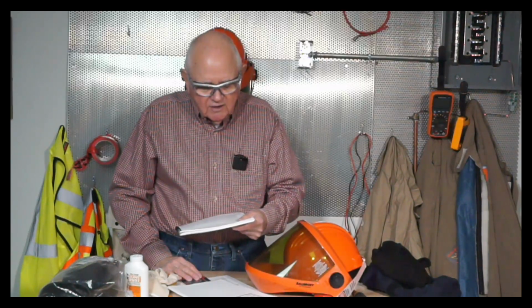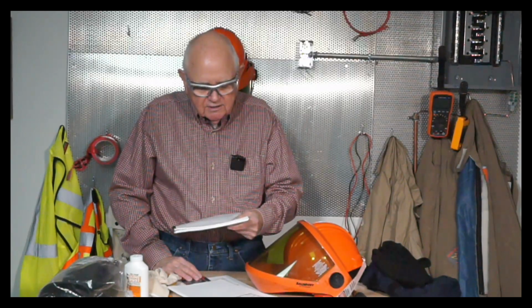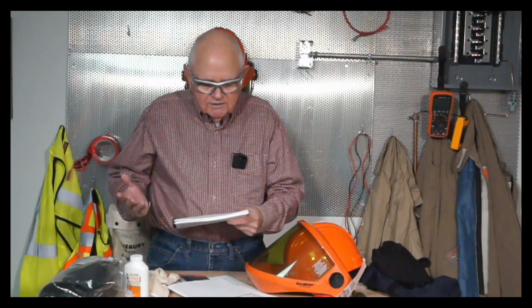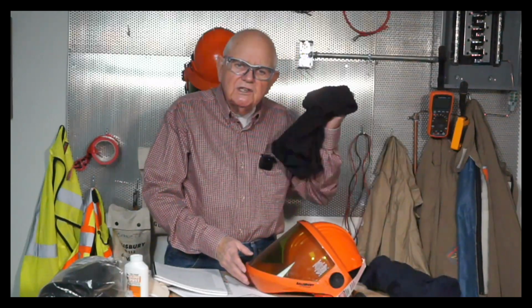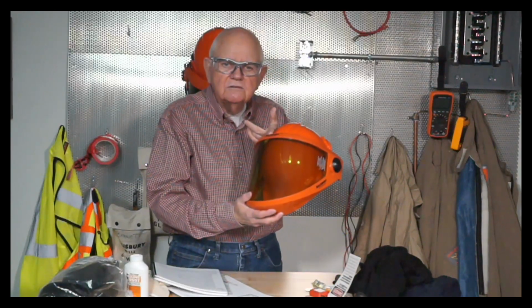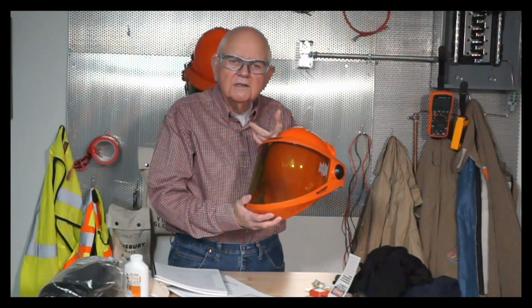It goes on and says arc-rated long sleeve shirt and pants, arc-rated coveralls, face shield or arc flash suit hood, arc-rated jacket, parka, and so on. It never says I have to wear a balaclava. 130.5(G) said I needed the balaclava. PPE category 1 says I just need the face shield. So, boss, what do you want me to wear? You've got two conflicting bits of information on your arc flash warning label. So anyway, that's one reason why we don't use those two separate systems or try to combine them in some way to tell people how to dress out. So use either the incident energy analysis or the PPE category method.